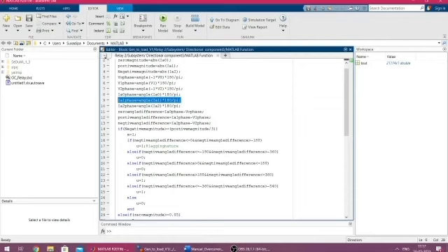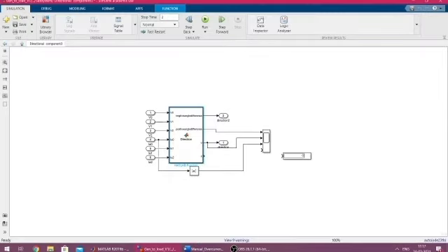In case the phase angle difference comes out to be negative, that is 0 to minus 180 degrees, it will be called a forward fault, and here the relay should trip. That is, the output of the directional relay unit will be binary 1. This we have defined inside this MATLAB user defined function. This is all about the logic of the directional relay subsystem.